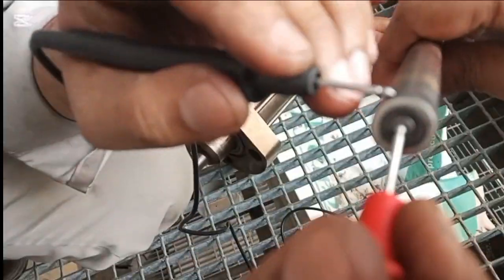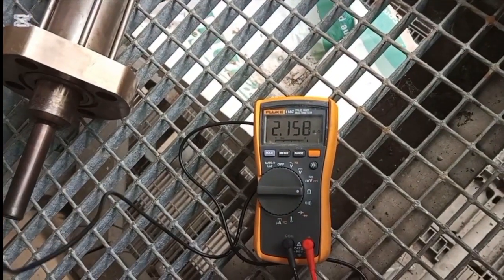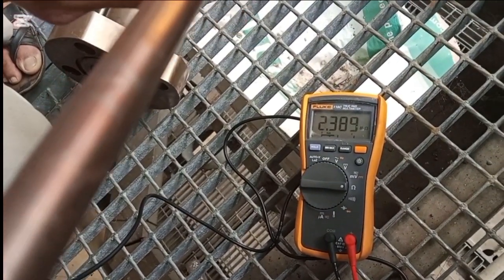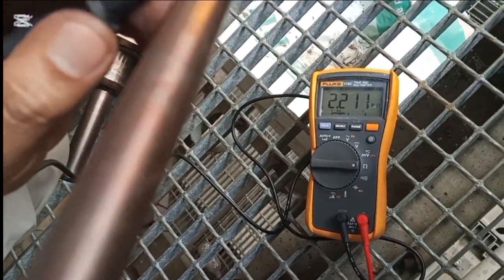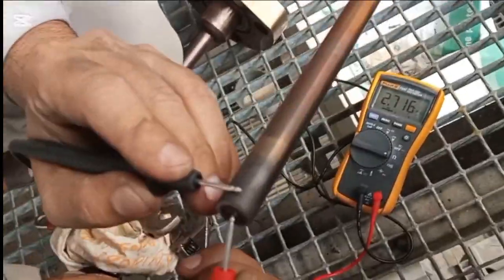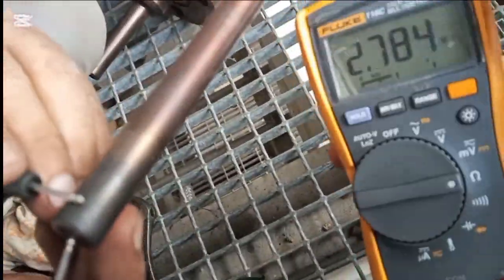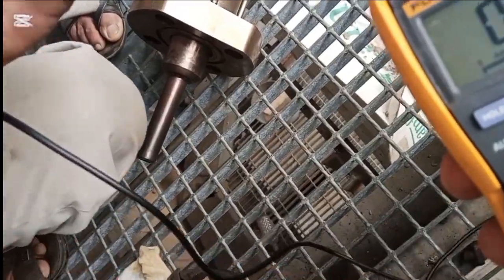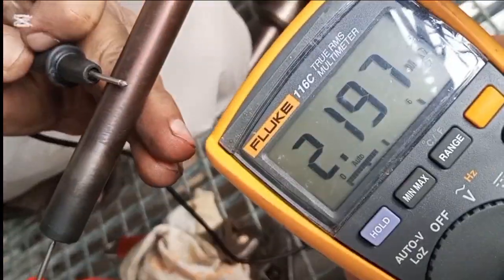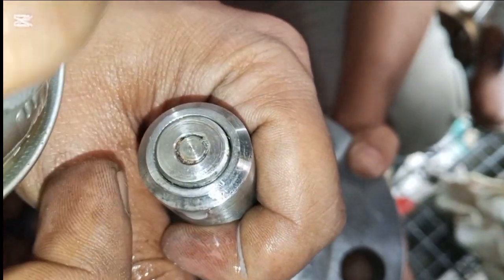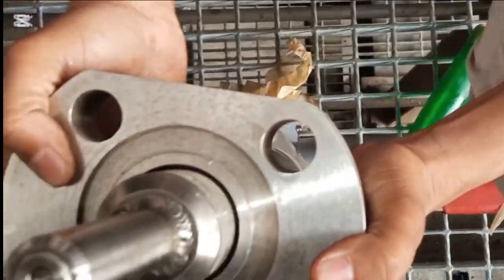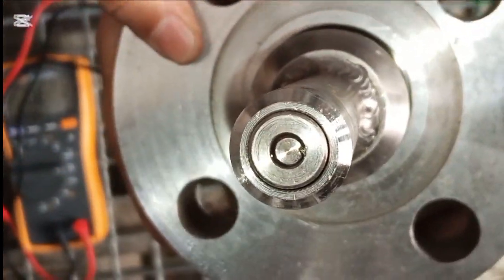And this is the electrode part. Inside this there is an electrode directly connected to the transformer output. At this stage we cleaned it and then we measured. We found that the continuity is not okay, so we took a decision to change this part, or this complete spark plug. This is our storage spark plug unit, and you see this is the new unit. It was in our storehouse.